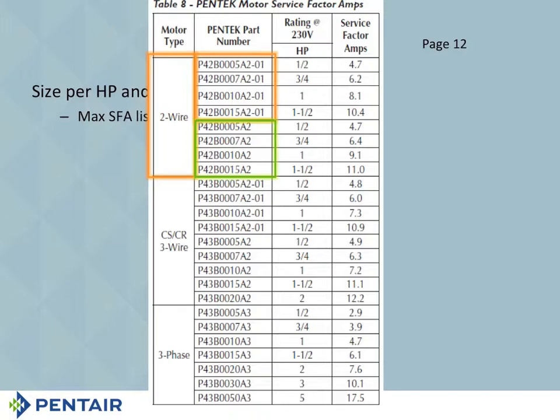So the difference in those motors there, and of course you'll notice it does make a difference in your amp reading too. And that's always very important to note. So you're going to notice that the service factor amps are a little bit different. For example, we've got the 1.5 2-wire motor there. If it's got the -01, the service factor amps are 10.4. If it doesn't have the -01, the service factor amps are 11.